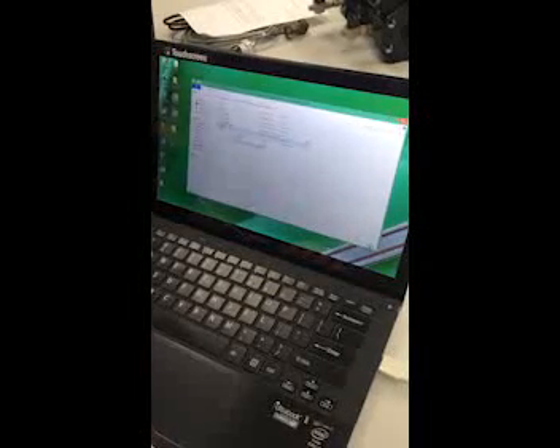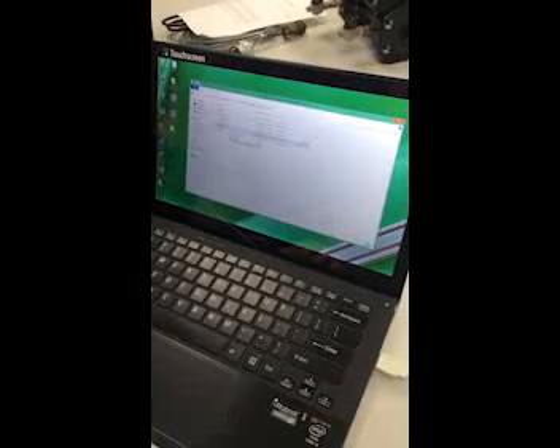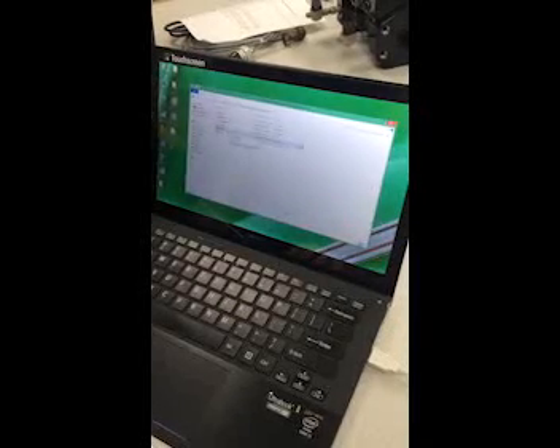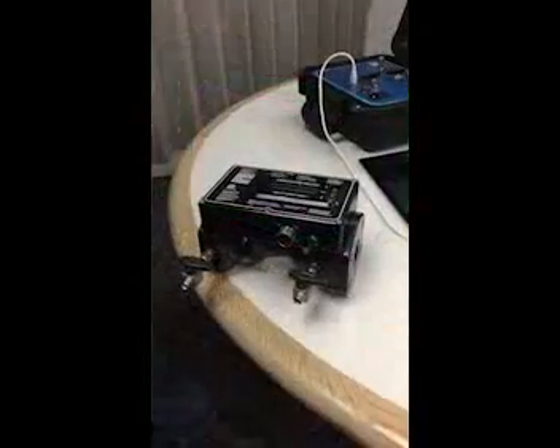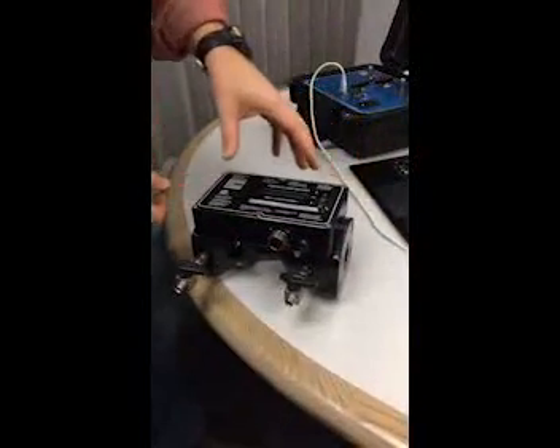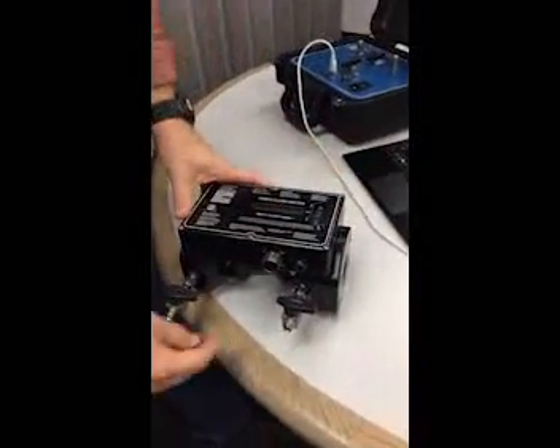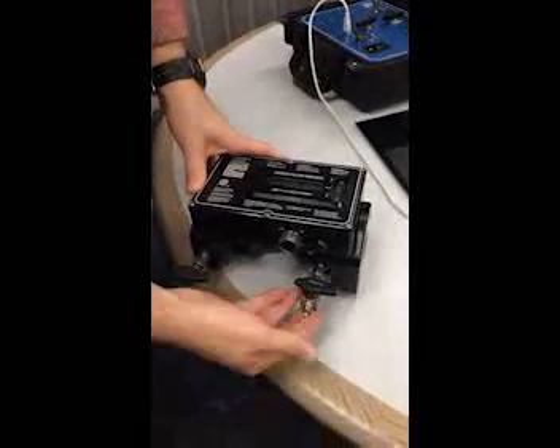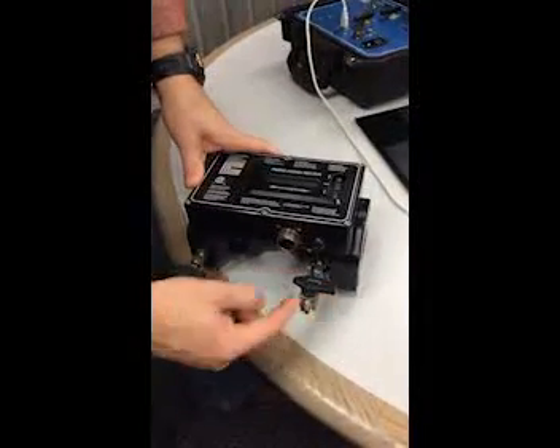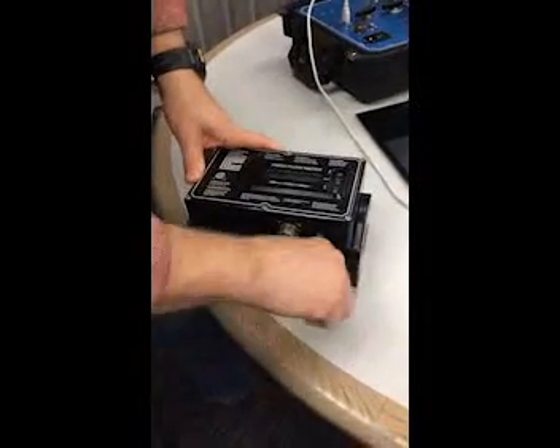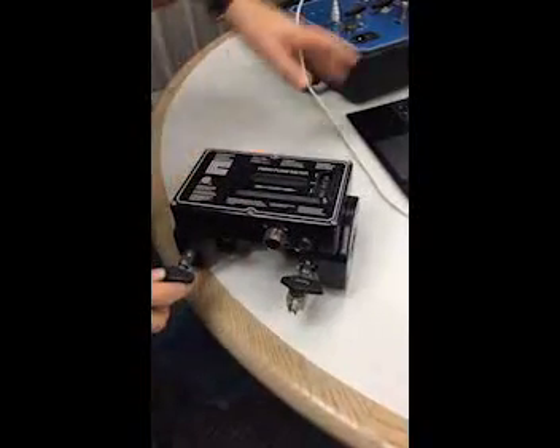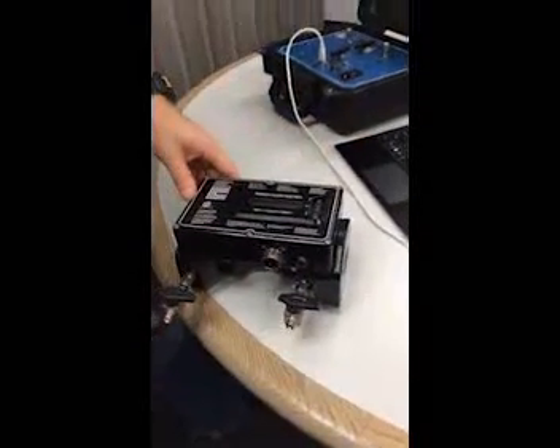It should be noted that once we do the initial setup, it can take up to approximately 5 minutes, and you do not need power to the FM50 calibration test set. So this can actually be done in your office before you head out to the field. Okay, so now if you're out in the field and you're on your FM50, you should already have these ball valves installed. Yours may look a little bit different, but the point is the ball valves are installed. So we're going to get ready to hook up the test set to the FM50.